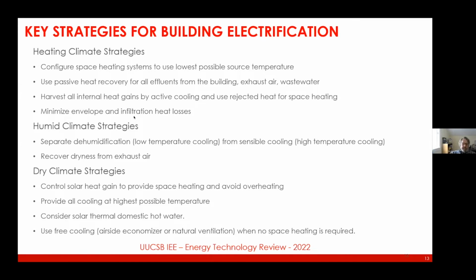And before we had condensing gas boilers, there was really no energy efficiency advantage to be gained by producing hot water at 140 degrees or 120 degrees compared to 200 degrees. But arguably the first cost of implementing a system, in terms of the size of the pipes, in terms of how much coil you have to have at the point of use to transfer the heat to the space, the first cost of heating with 200-degree hot water is much less than the cost of heating with 100 or 120 degree hot water. However, when you get into an electric sourced heating alternative, using some type of refrigeration cycle to make the hot water with heat sourced from either the outdoor air or inside the building, you'll be much more energy efficient if you can do that with a low temperature as compared with a high temperature.